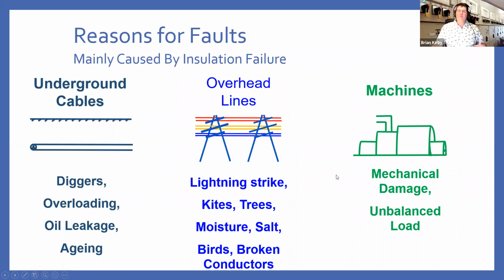So for different parts of the network, there are different causes of faults. Underground cables: diggers, so people digging up, I've mentioned previously, but also overloading. A cable may have been installed originally to supply, say, a small residential area, and over time more and more homes have been built and the load has gradually increased, and ultimately you unintentionally overload the cable. Leakage into the soil can directly affect the insulation. It can get in and break it down and cause faults within the cable, and also the aging of the cable itself. Over time, it will just deteriorate. So there needs to be some sort of maintenance and plan for that.